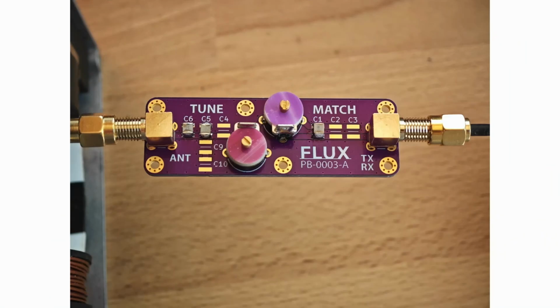There's this thing in RF called a Q factor, which is essentially a quality factor, and it's how much you amplify your signal. What we really want to do is run a really sharp Q factor, which amplifies the signal right at the frequency we care about, and knocks out all of the noise apart from in different places. So we had to make up these fun little boards where you use your tuning and matching capacitors. One of the problems is, for the tolerances you're talking about here, capacitors off the shelf don't work that well. Well, they work fine. It's just they're not the number they said. The tolerances are so large.